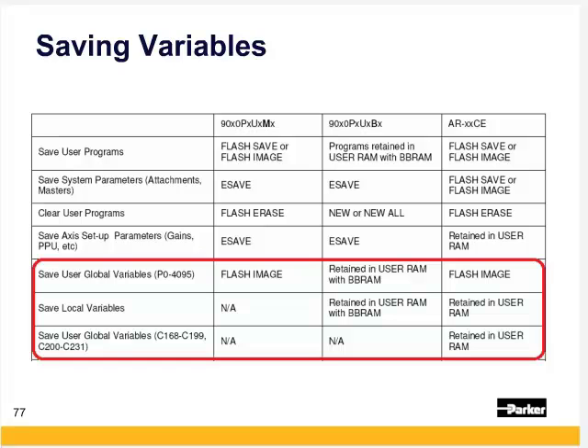For the battery-backed RAM units, the user global variables are retained automatically as well as local variables. For the ARIES controller, the user globals would require a flash image, but local variables and user global variables C168 to C231 are non-volatile.